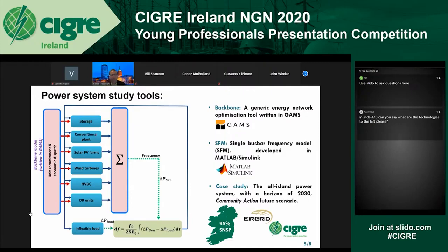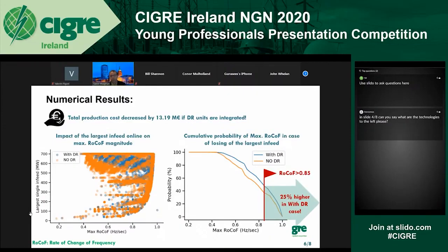Numerical results show that integration of demand response units results in a 13 million euro cost reduction. However, deployment of demand response units as a source of reserve resulted in deterioration of RoCoF, as illustrated in the figures. Look at the left figure in this slide. You can see that in case of losing the largest single infeed, the blue points, which represent the case with demand response units, tend to the right, which implies that we would have a higher rate of change of frequency if we consider demand response units.